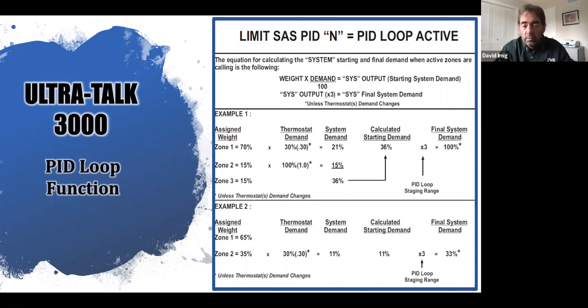So 100% times 15 is 15. Now I add zone 1 and 2. My starting system demand is 36%. And I'll show you what that means here in a minute. What's 36%? But that's where I start, at 36%. Now my PID loop gives you a range, meaning I start at 36, but what do I do from there?